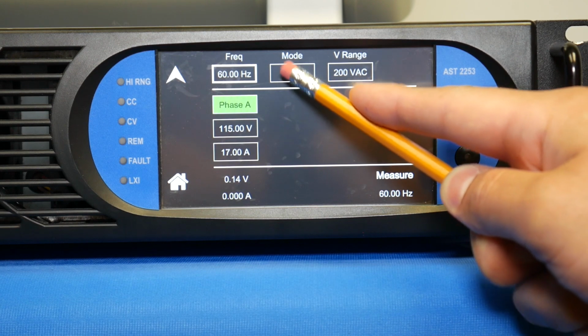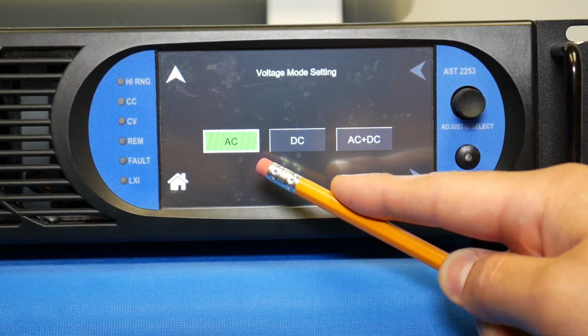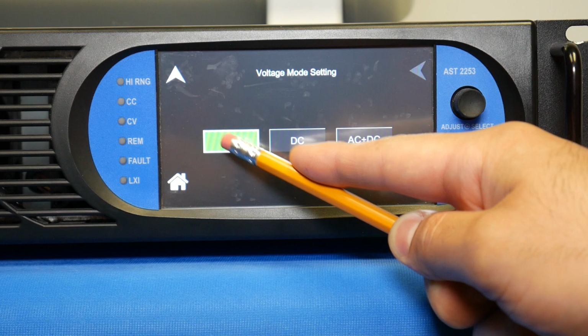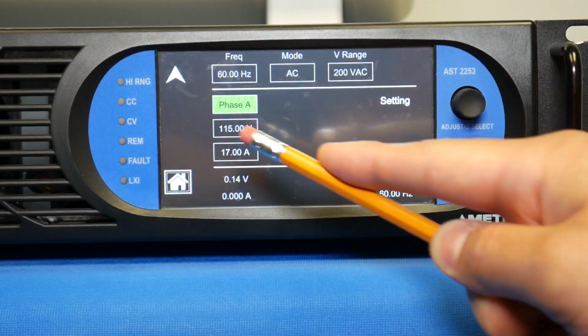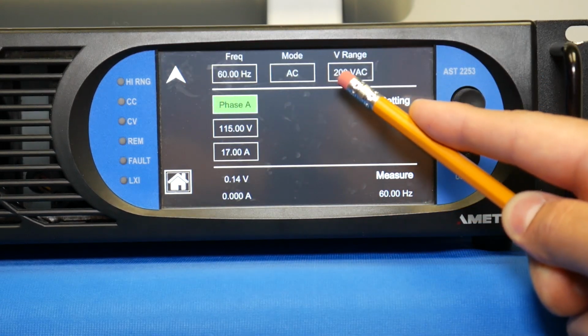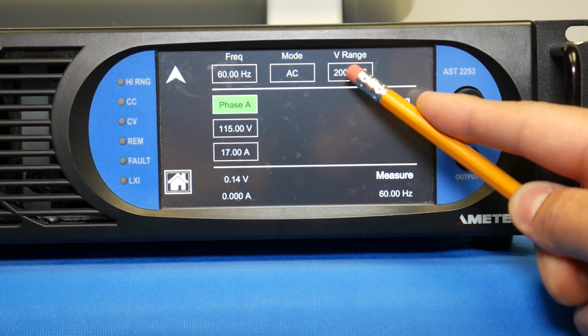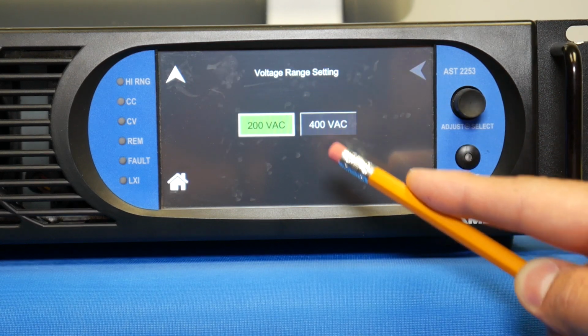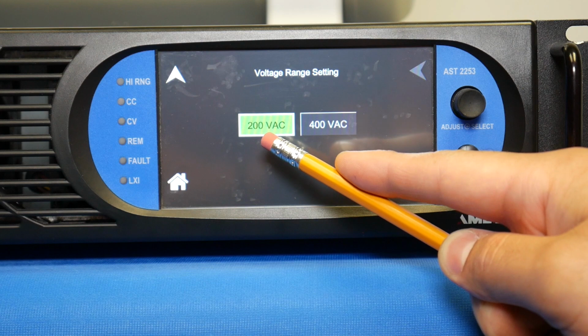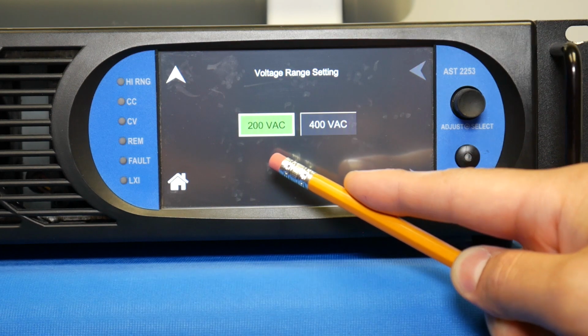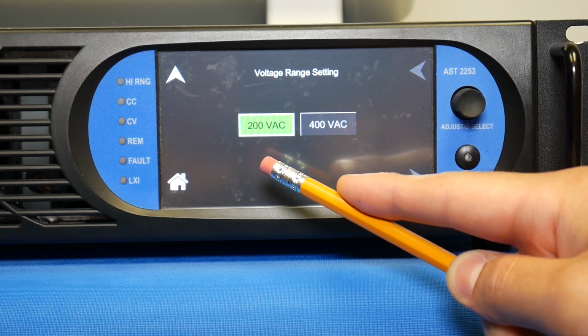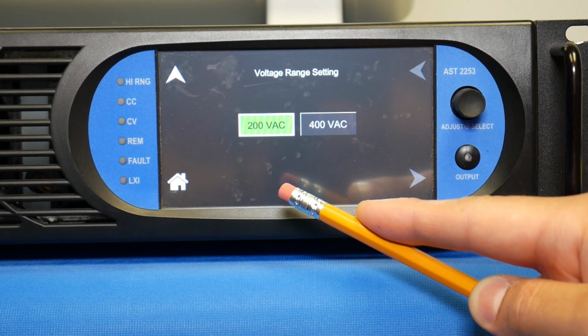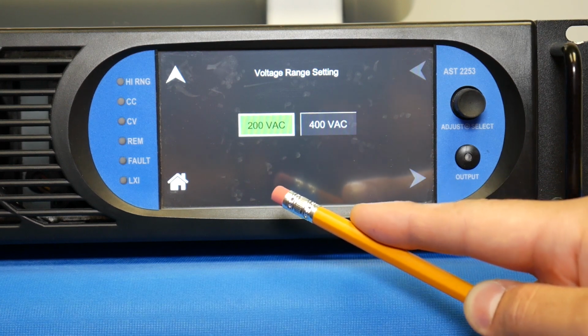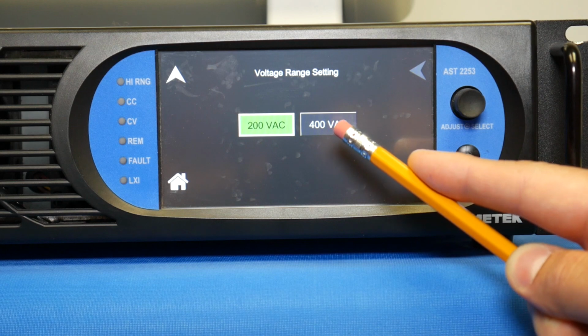Afterwards, we verify that we're running the Asterion on AC mode. Select, go back using this button, and now we confirm the voltage range. We're going to hit this button, select 200 VAC as the voltage range since we are conducting a low voltage range test. If we were selecting a high voltage range test, we will select 400 VAC.